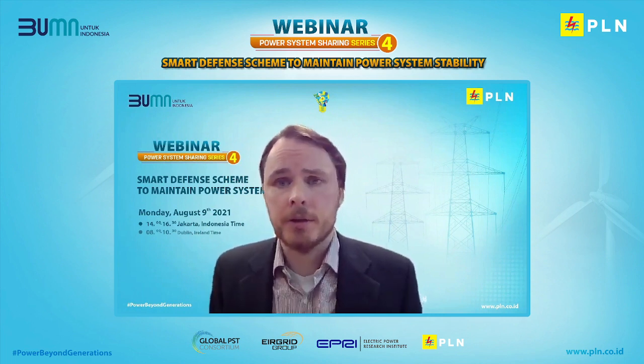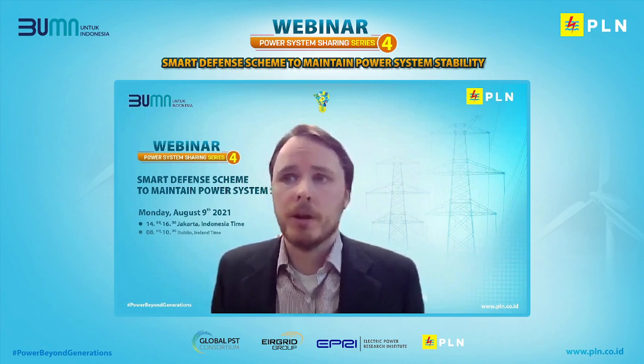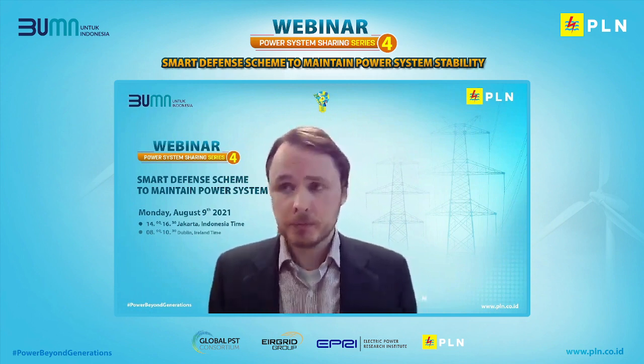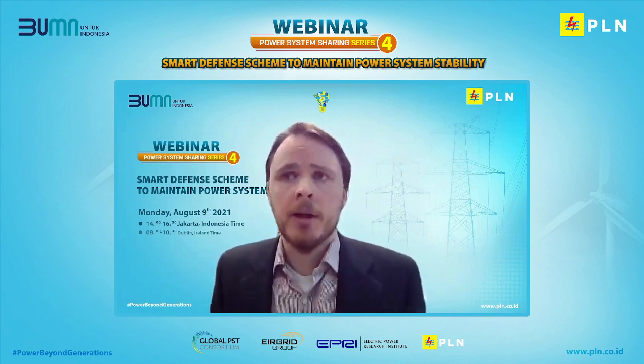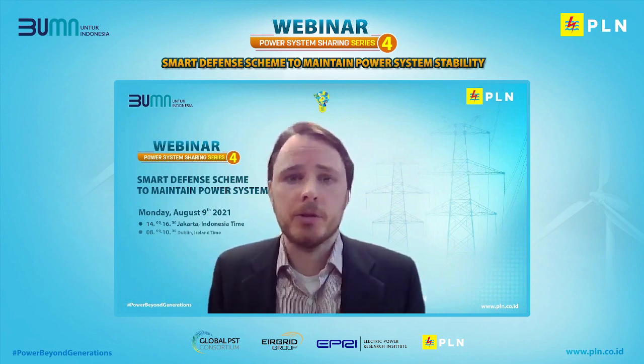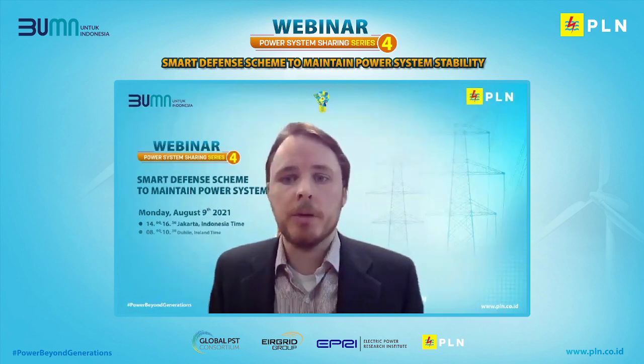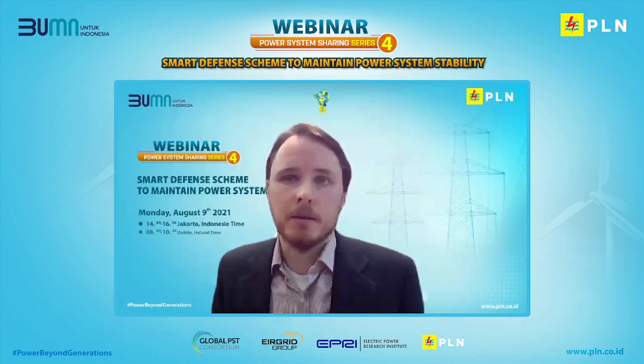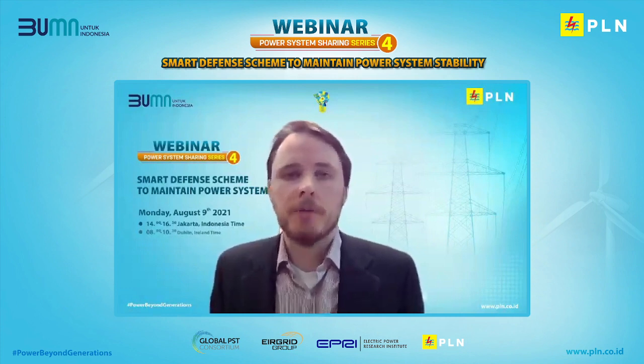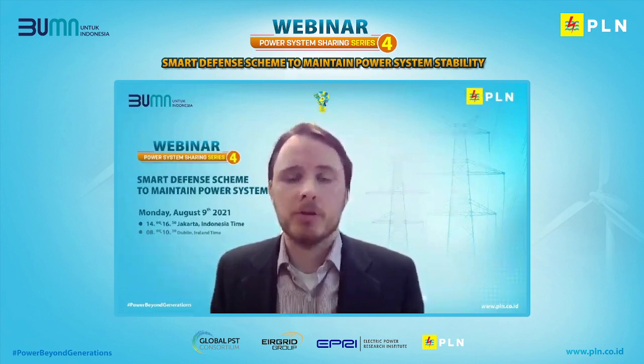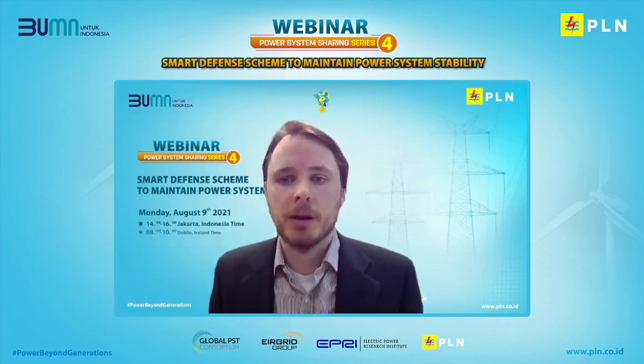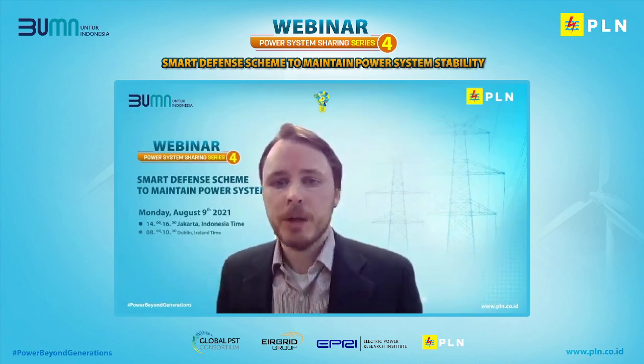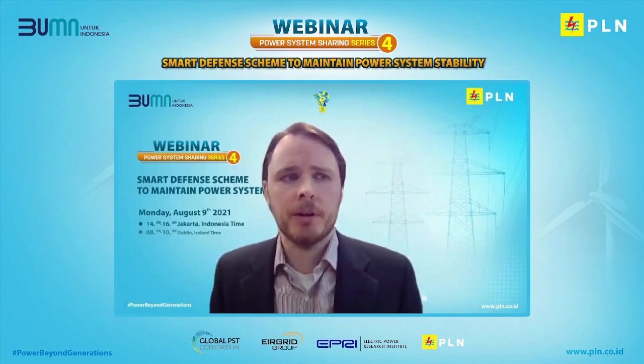And in EirGrid in Ireland, they implemented such a scheme before, where they had line overloading in a particular area. If the loading persisted, it would cause the generators to run back. If you have a frequency stability problem, however, then you will typically have to rely on hydropower plants, pump storage, or battery energy storage to quickly mitigate the overload. I hope that answered the question usefully.